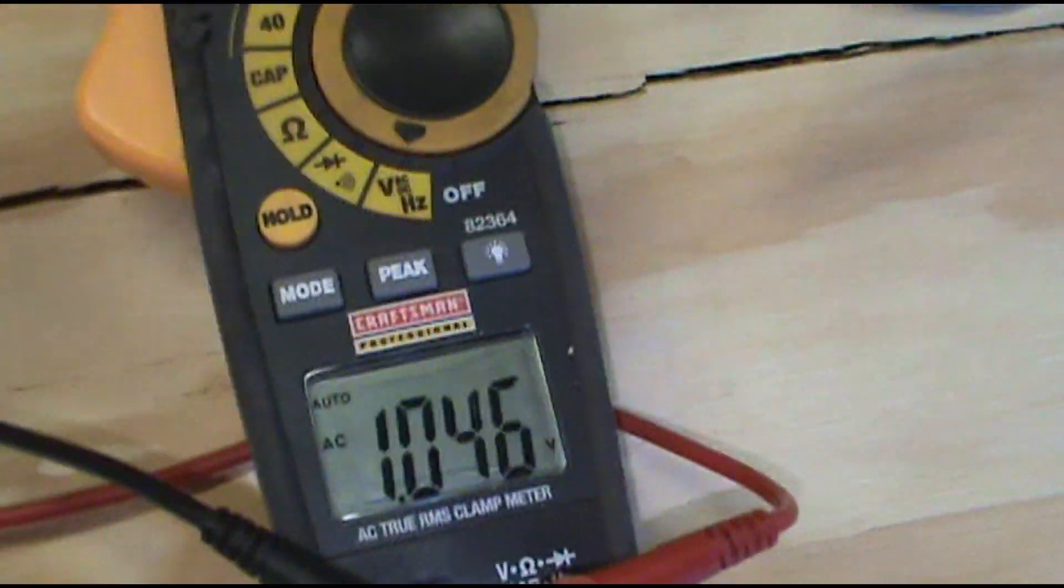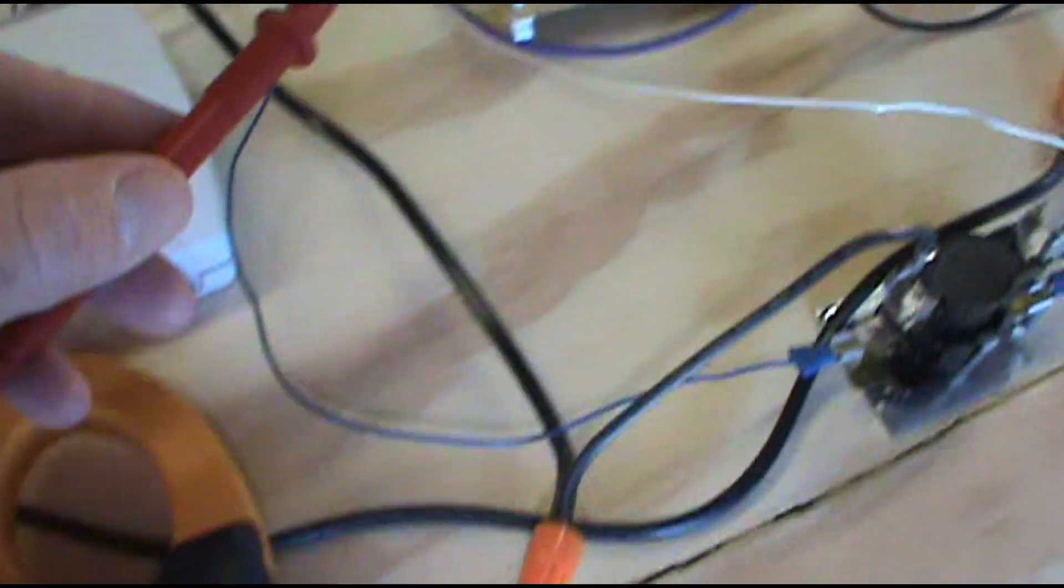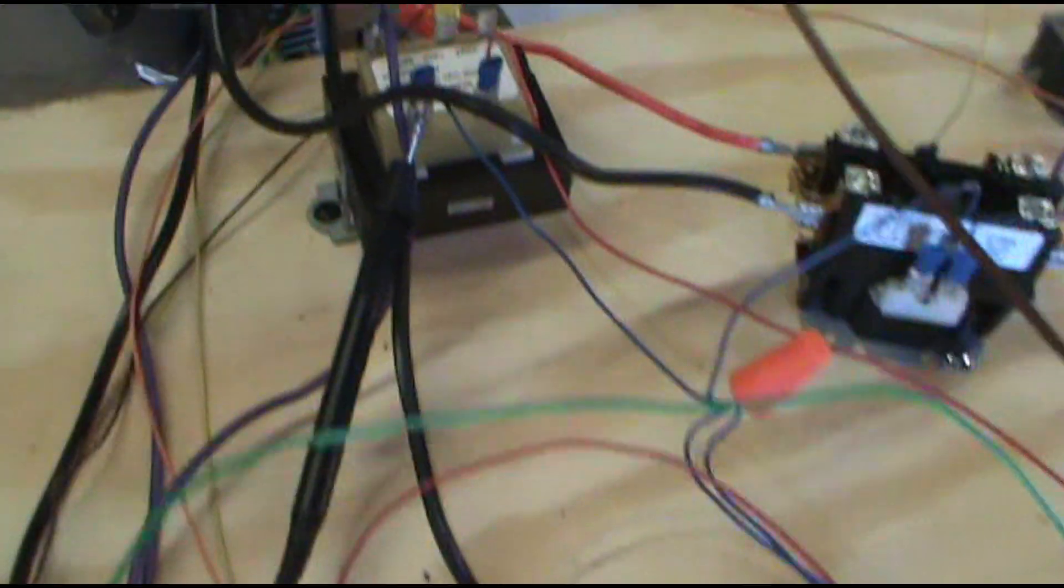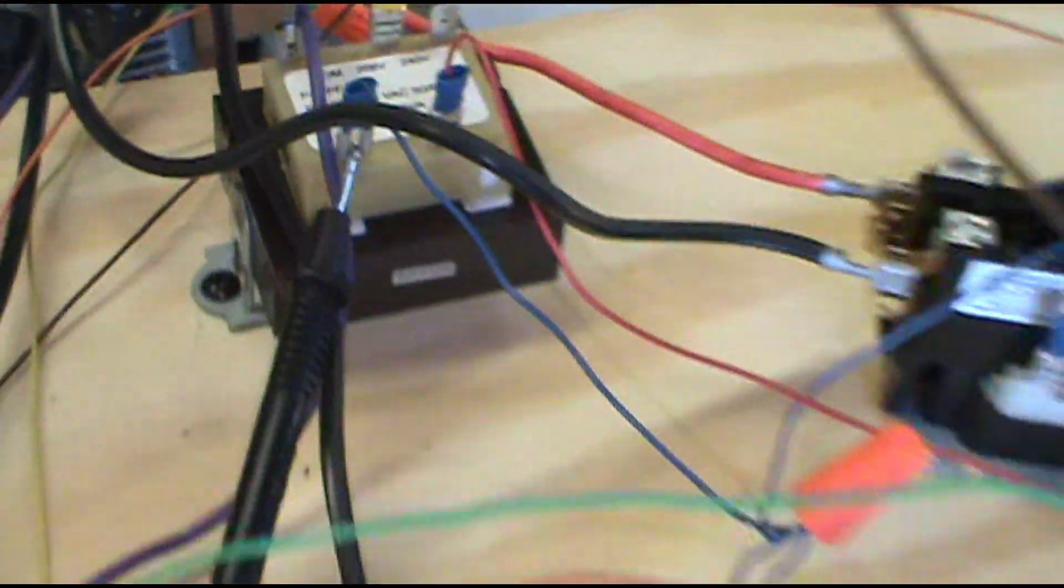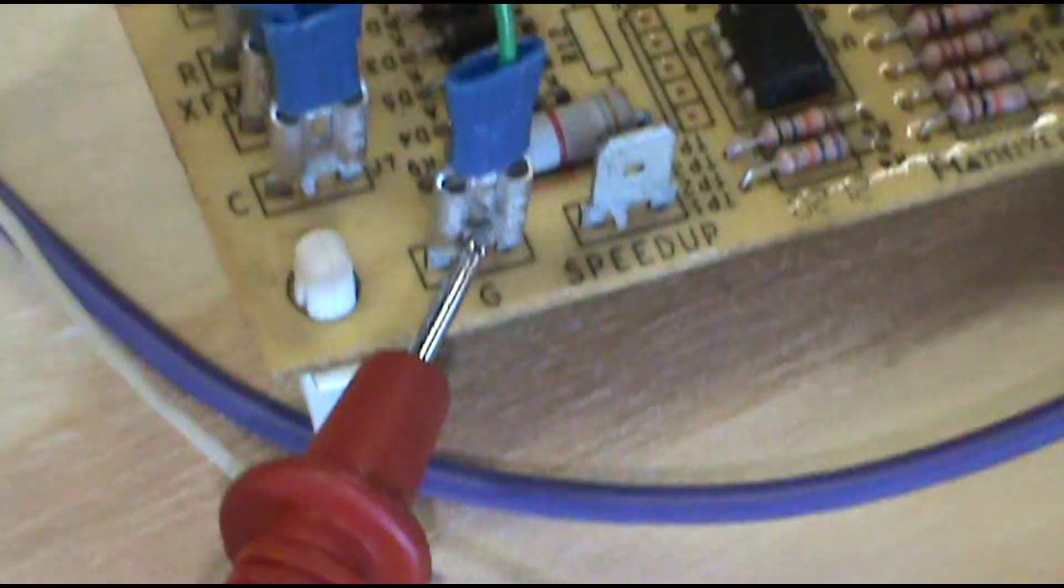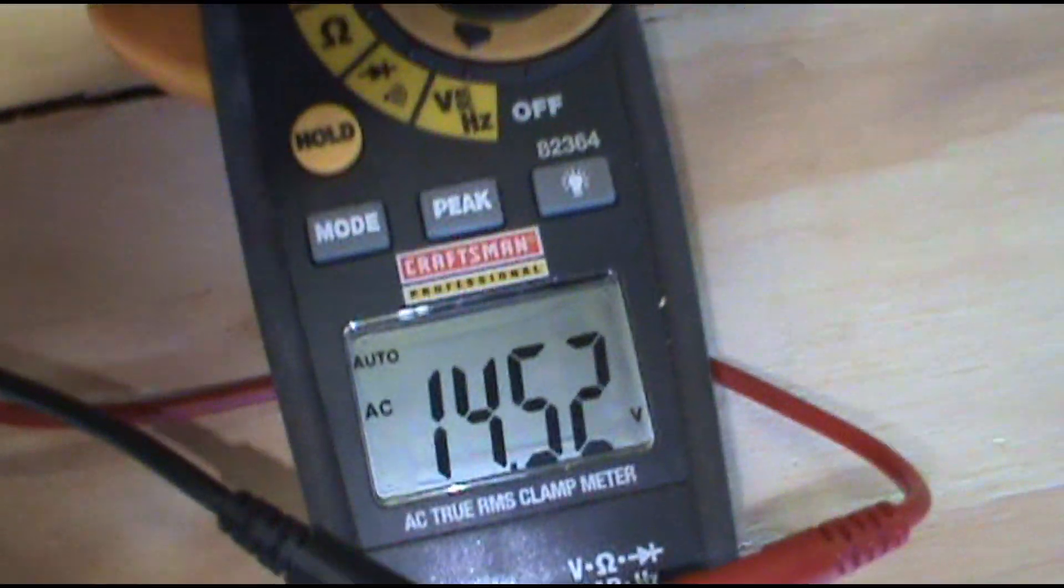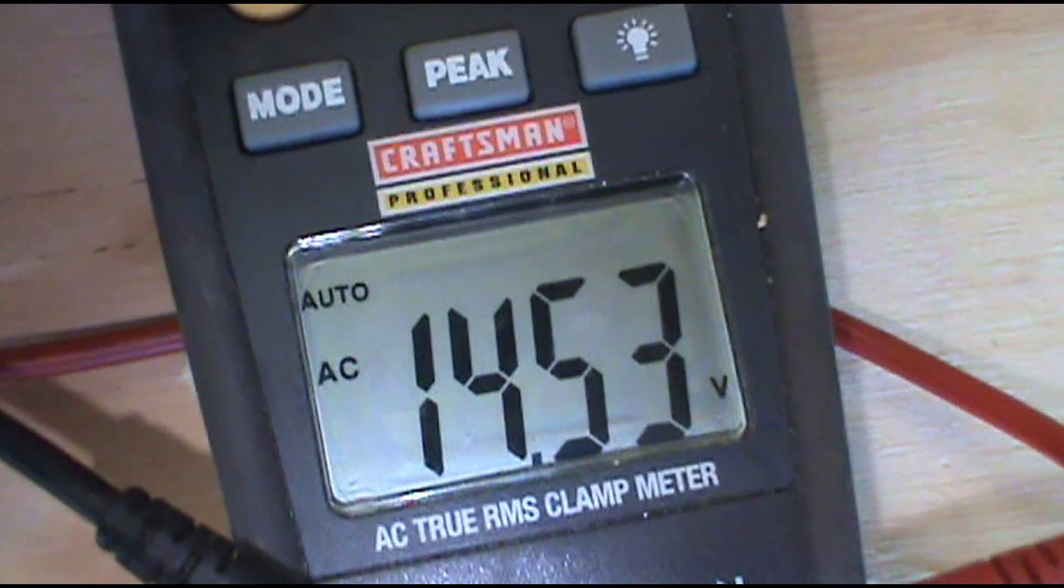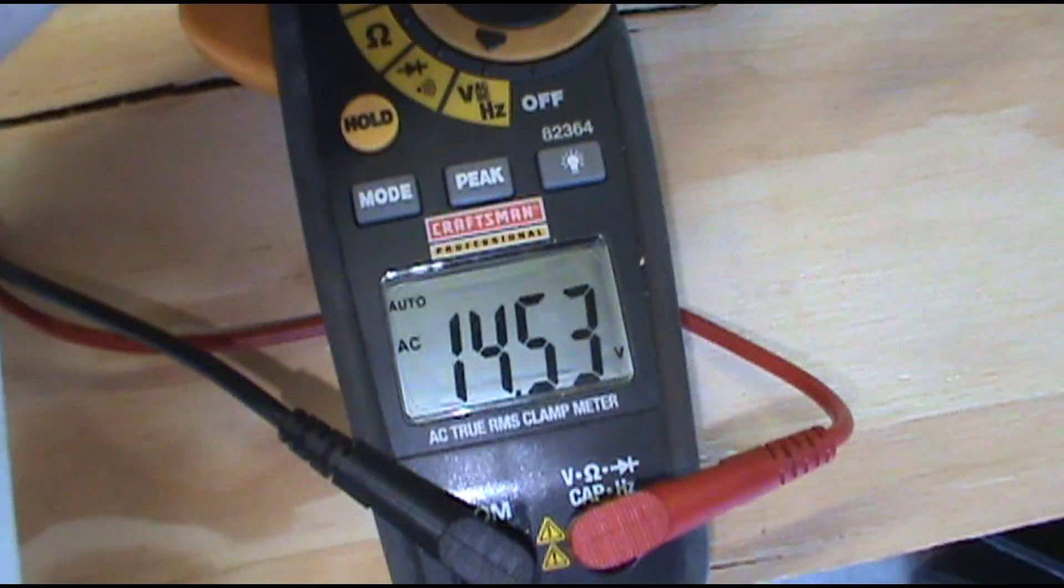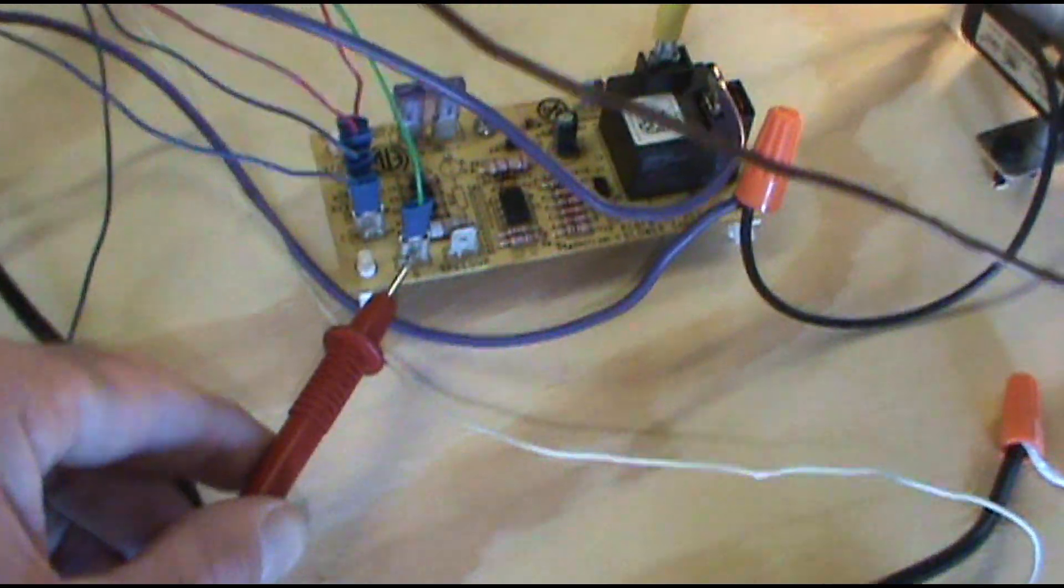First thing I would do, set my meter to the volts. Then I would touch one to common there on the transformer. See I got one lead on the common and then one lead on the G here, that's for the fan. You want to make sure it's calling for 24 volts. I'm not going to get 24 because we're running on 120 here, but I got 14. So I got voltage, that's good. Out in the field it would say 24 volts or a little higher sometimes, 26, 28. So we're good here.